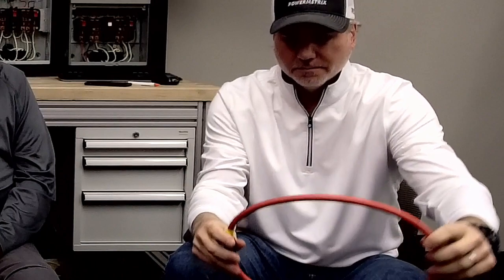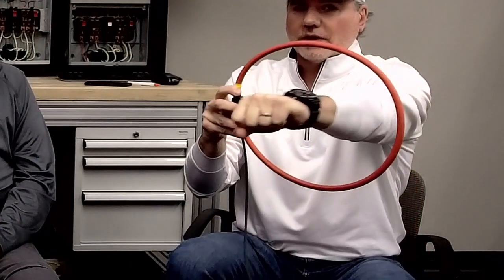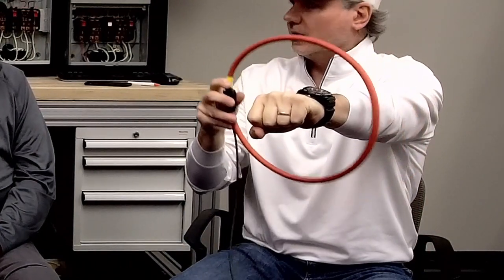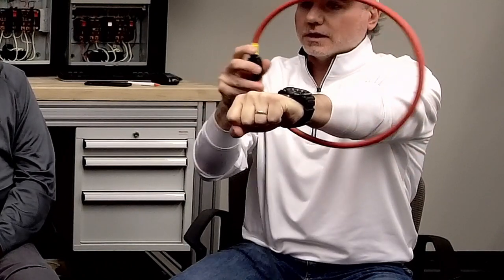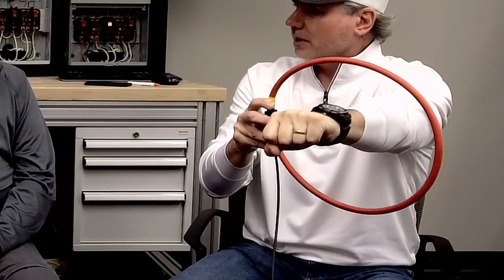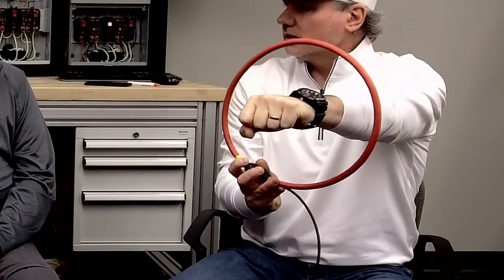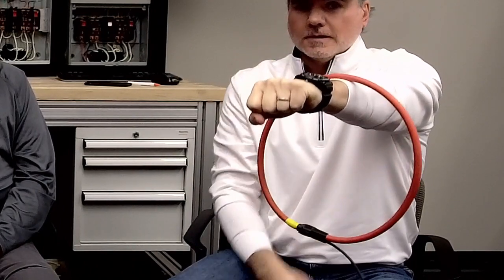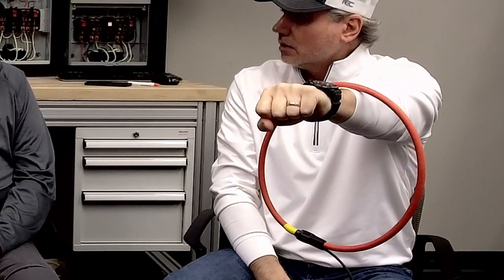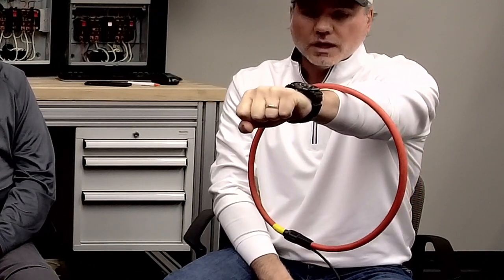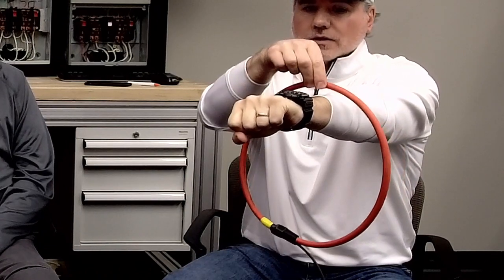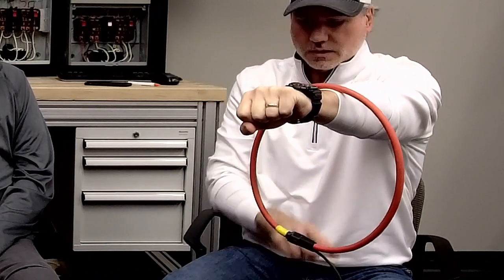When we do a calibration on them, we can calibrate them with that conductor anywhere in that loop. As you move that conductor in the loop, you'll get different readings on that primary current. Most people have told us that most of the time when they're out in the field, they're hanging their probe on a conductor. So when we calibrate these in-house, that's kind of our sweet spot, up near the top of that window, as far away from that connector as possible. So that's really your sweet spot. It's not necessarily in the center anymore, okay?